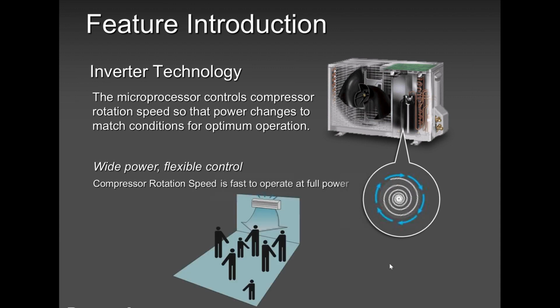But guess what? The load has increased. Now the load has increased. The sensor has sensed it. The sensor at the indoor unit sends a signal to the outdoor unit. Hey, I need more juice. I need more energy. I need more pumping. So that sensor sends a signal outside to the EEPROM. The EEPROM tells the compressor, guys, hey, ramp it up. I need more energy. And that's where you find the compressor going higher and higher. Okay?